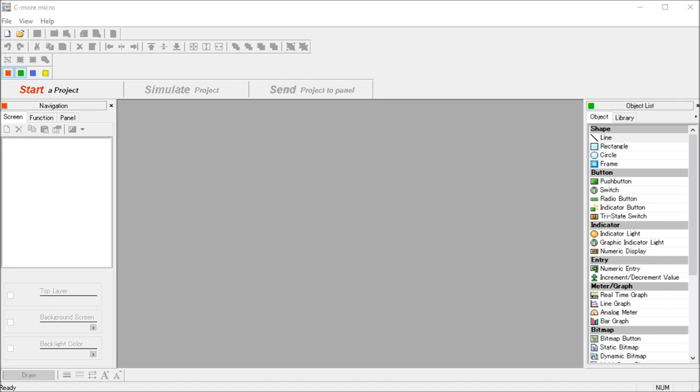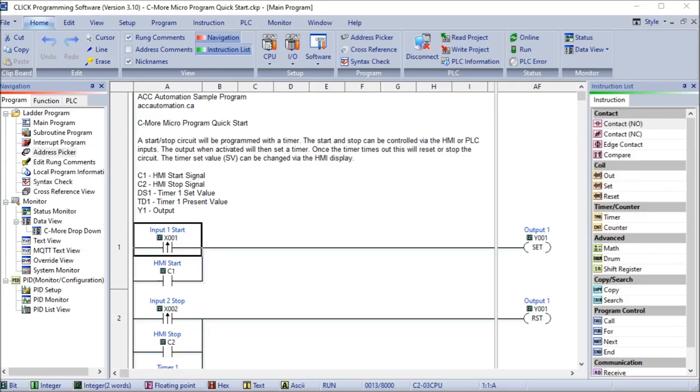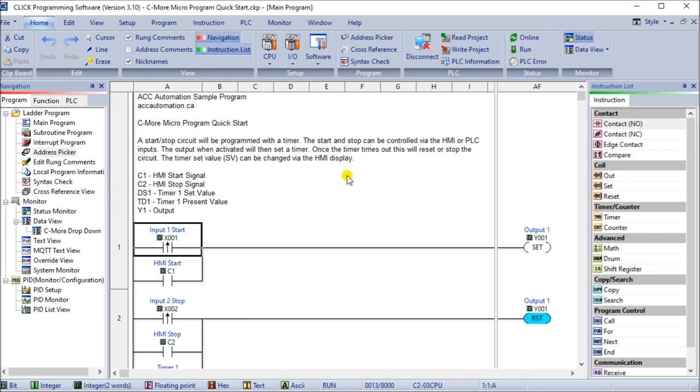The first thing that we'll do is look at the program development in the ladder logic. In our case here we're going to be using the Click programming software which we have right here, and we are currently communicating online. We can just hit the status so you can see that. Now what we're going to do is use a start stop circuit programmed with a timer. The start stops can be controlled via the HMI or PLC inputs. The output when activated will then set a timer. Once the timer times out, this will reset the stop and or stop the circuit. The timer set value can be changed via the HMI display.